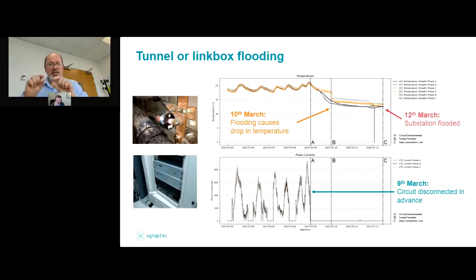But the point is this: DTS and DAS are only monitoring the structural integrity of the cable itself. What we're trying to do is infer the health of the cable by understanding the electrical stresses going through the inside of the cable, looking from the point of weakness, which are these joints and terminations.